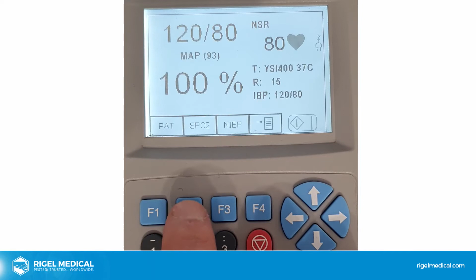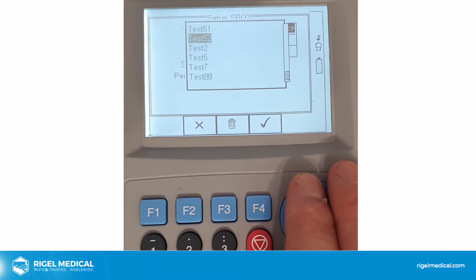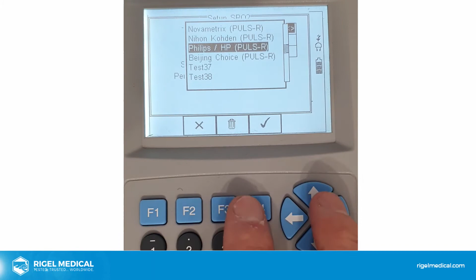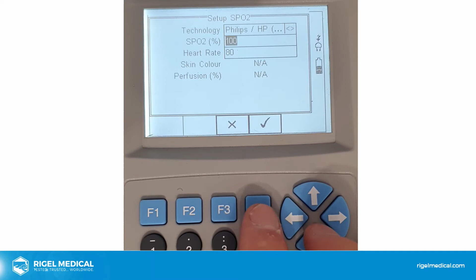That's the patient test settings. We go back to home. We can then set SpO2. That's already on the correct setting. Sometimes it will be set to settings that are without the pulsar. So on here, we've got Philips monitor, which is the monitor we'll be testing today. But because we're using the pulsar, we want to set it to Philips HP pulsar. 100% SpO2, heart rate 80. Keep it like that.